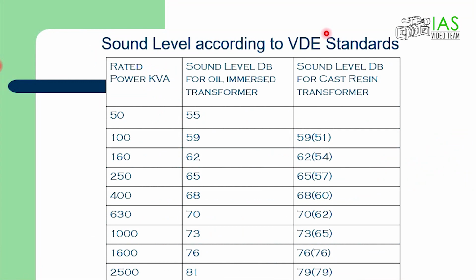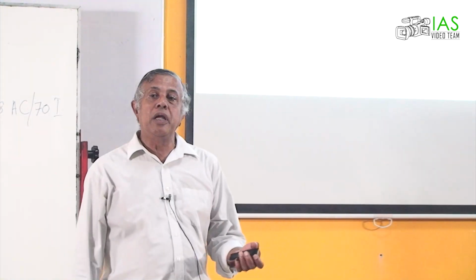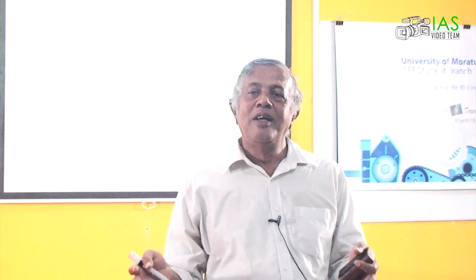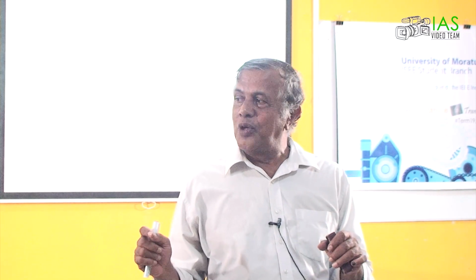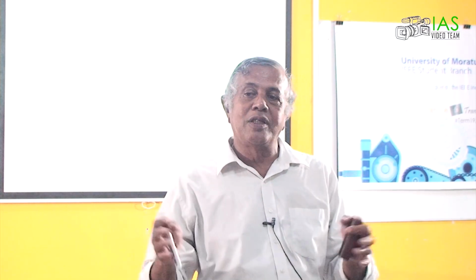Sound levels according to VDE German standards are given in this list. So with 50 kVA, and now in Germany they have standards. If I complain, this transformer annoys me, they have to either remove the transformer legally, or they have to put a sound attenuation canopy to the transformer. So they normally put a sound attenuation canopy to the transformer if somebody complains.